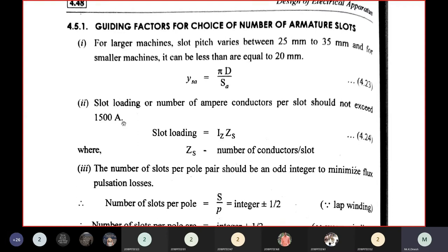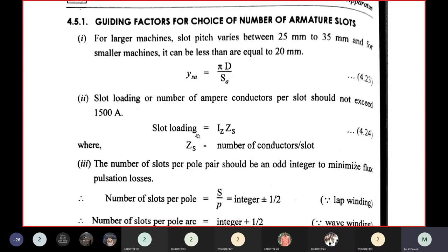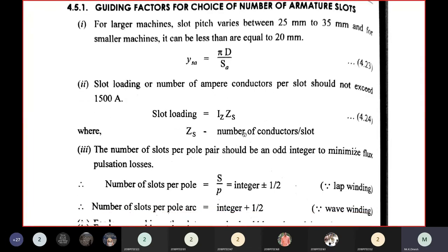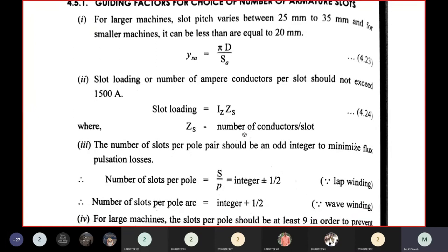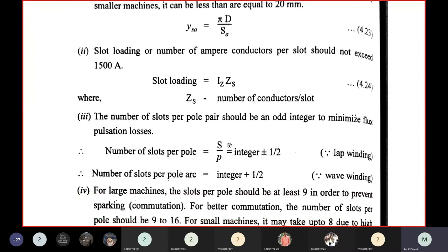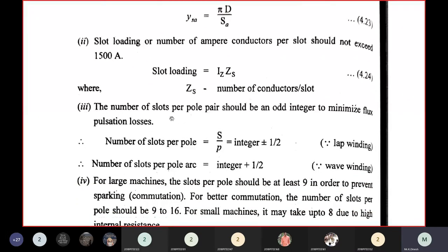Mathematically, slot loading equals the current times number of conductors: IZ × ZS. The third guideline is that the number of slots per pole pair should be an odd integer to minimize flux pulsation losses.